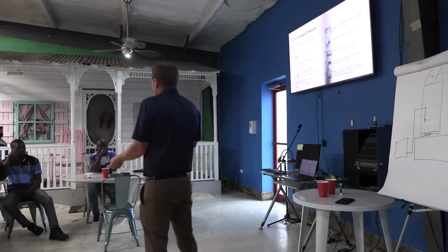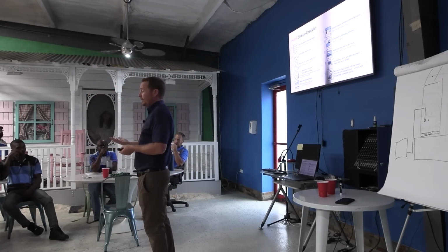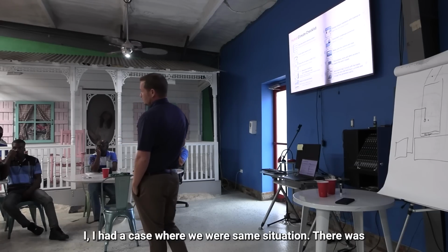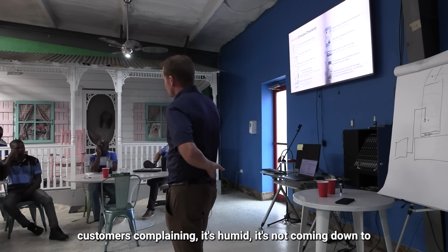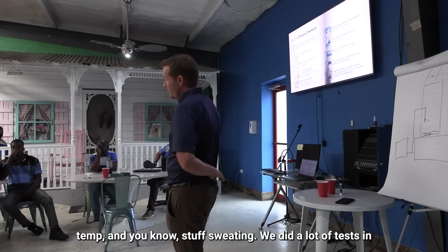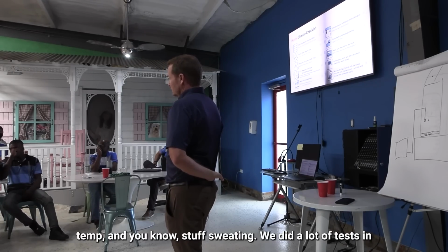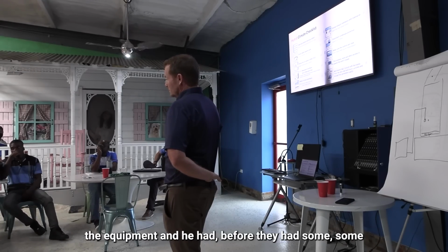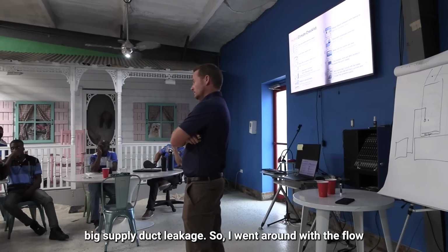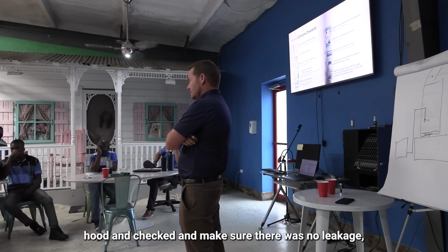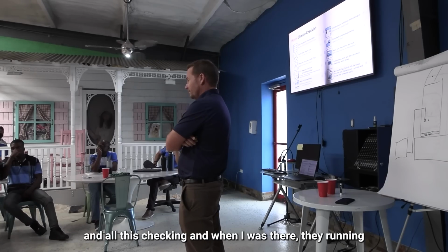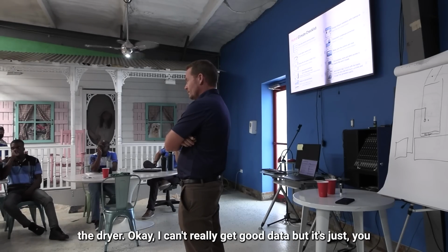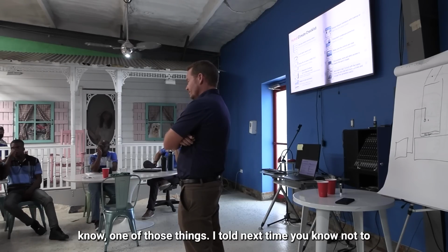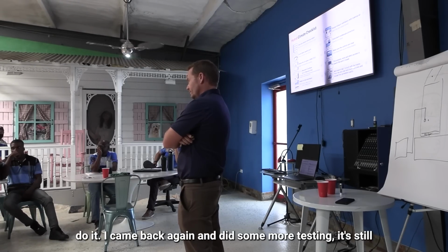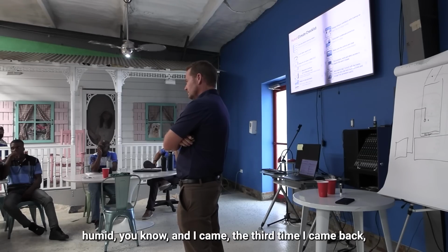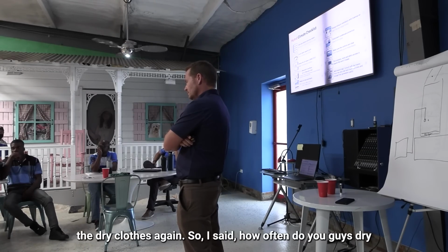Even a dryer is discharging air out and drawing air in. That's another big one. I had a case where customers were complaining it's humid, not coming down to temp, stuff sweating. We did a lot of tests on the equipment, and before that they had some big supply duct leakage. I went around with a flow hood, checked for leakage, did all this checking. While I was there, they were running the dryer, so I thought, okay, I can't really get good data, it's just one of those things. I told them I'd come back. I did, did more testing, and it was still humid. The third time I came back, they were drying clothes again.